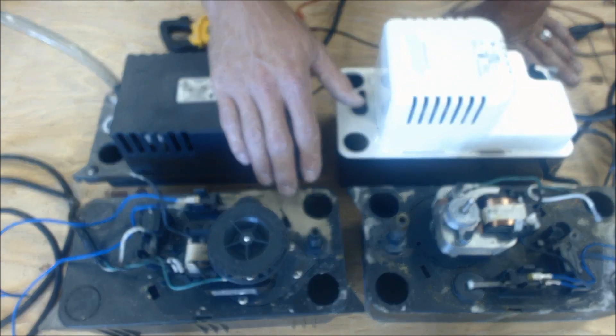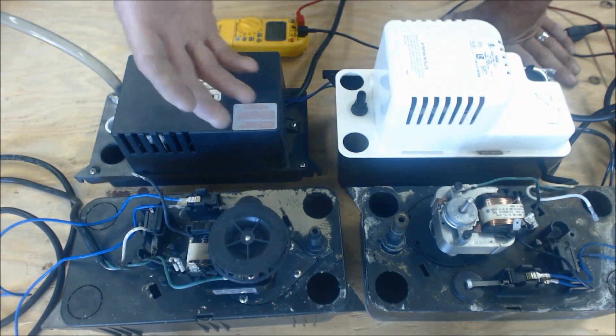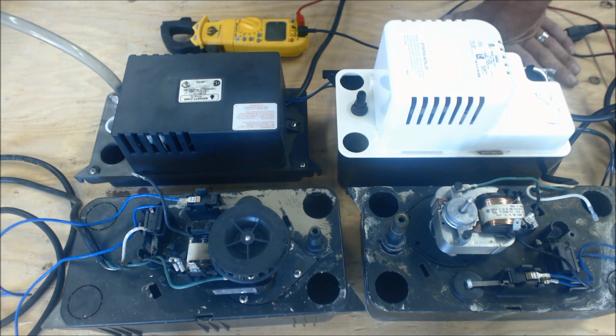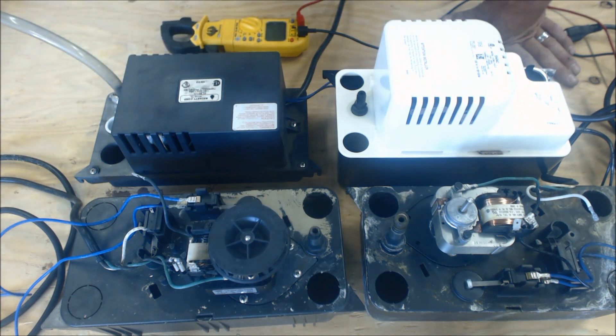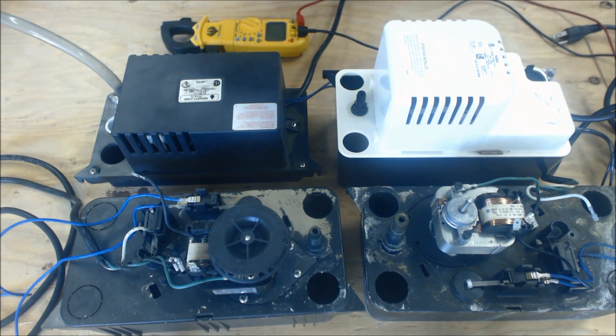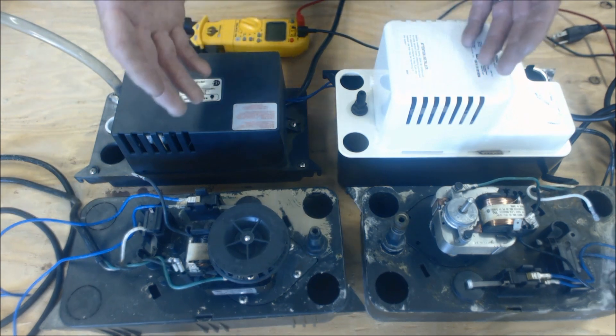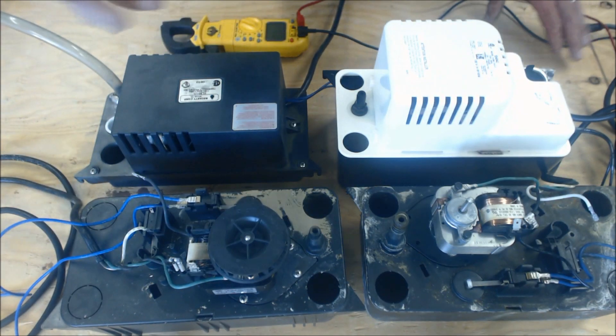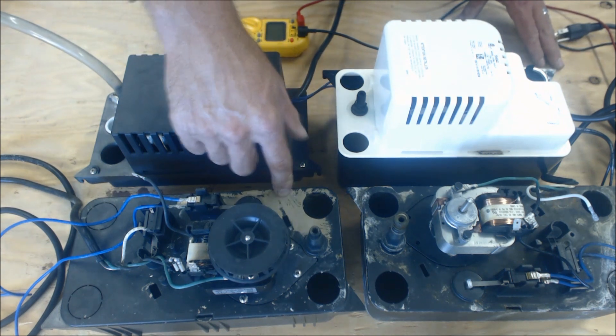Typically you don't use condensate pumps unless you don't have the potential for pitching your condensate line just due to gravity. So when you can't get away with pitching it by gravity with your three-quarter inch PVC condensate line, you use a condensate pump.